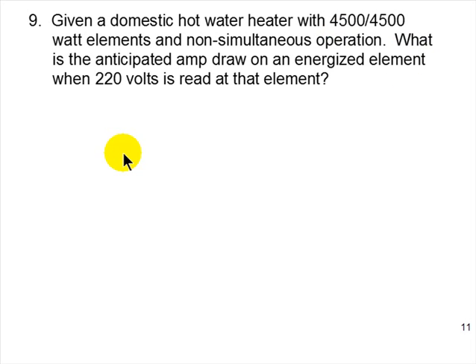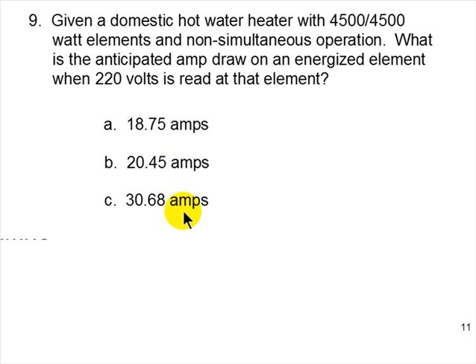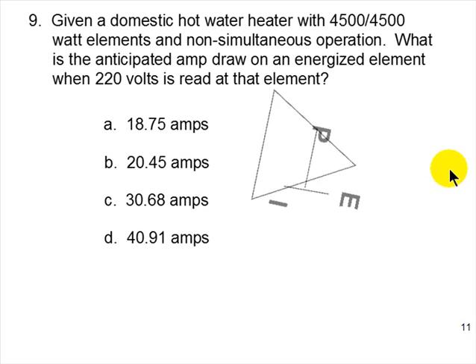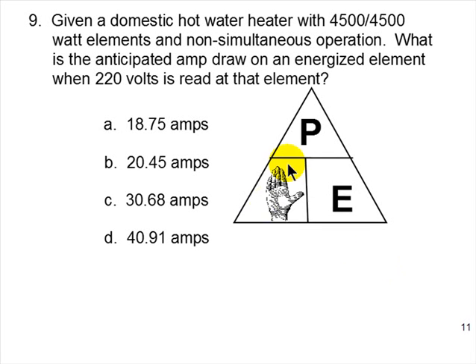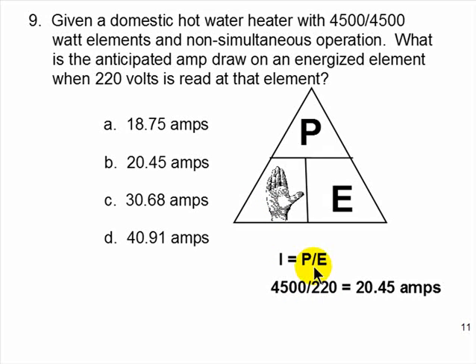So given this situation, what is the anticipated amp draw of an energized element when 220 volts is read at the element? Okay, well, 18 3/4, 20 1/2, 30.68, or almost 41 amps. What are you going to read? You can determine this easily. What are we solving for? Amperage, isn't that what they're asking about? You're going to divide the voltage, which we know, into the wattage, which is given. So if we're using 4,500 watts, we can divide P by E, 220, and we can expect to see 20.45 amps on our amp meter or our clamp-on ammeter.